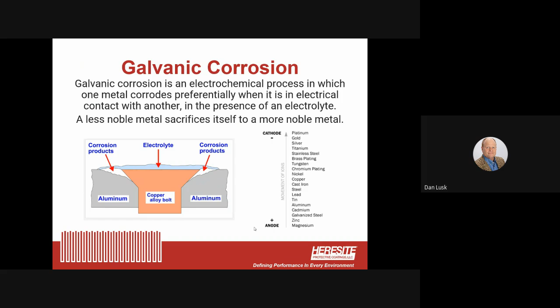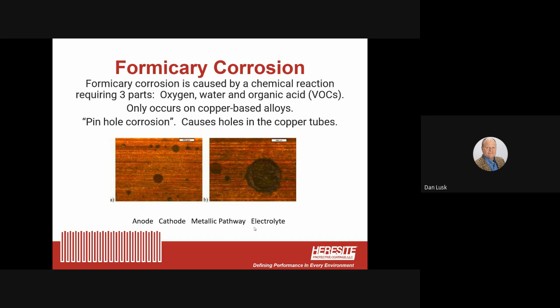We also deal with formicary corrosion. This happens with copper, where oxygen, water, and organic acids combine and create what's also called pinhole corrosion. So if you have a copper tube with a hole or leak in it, it's usually due to formicary corrosion.